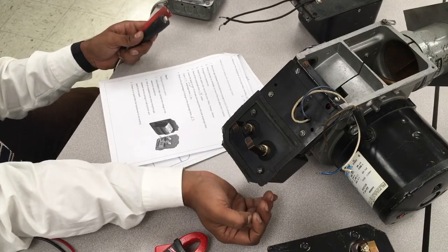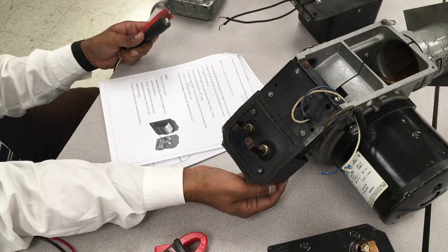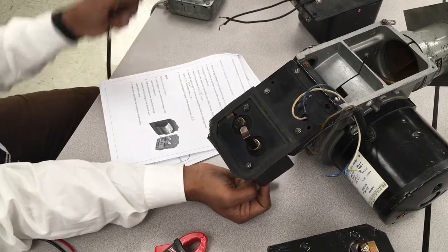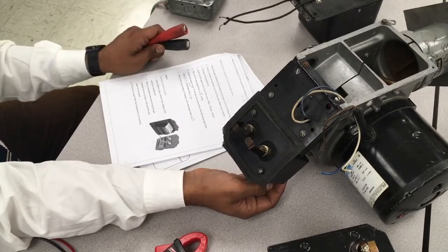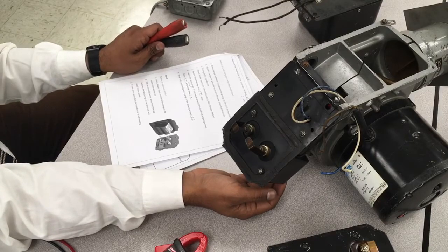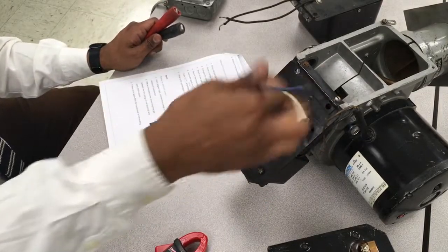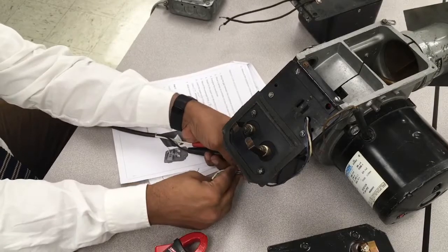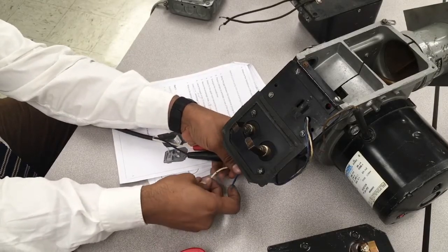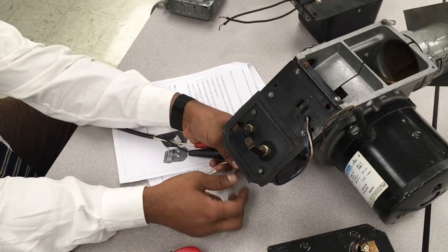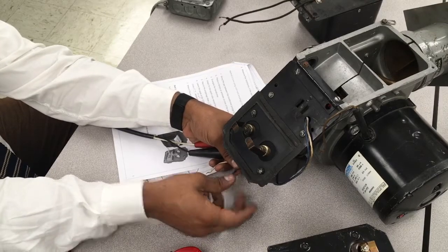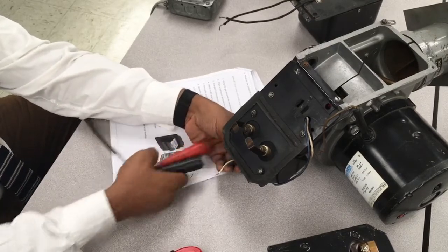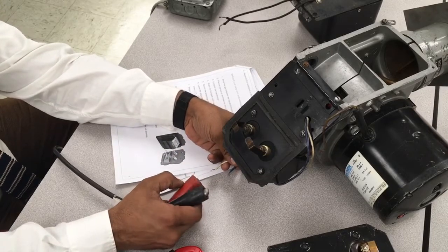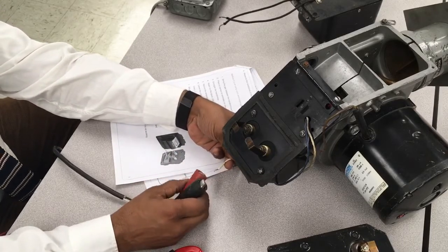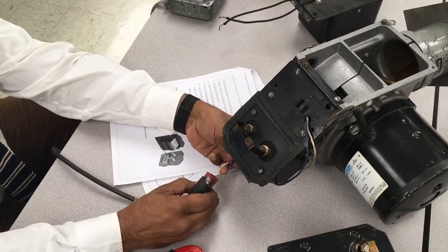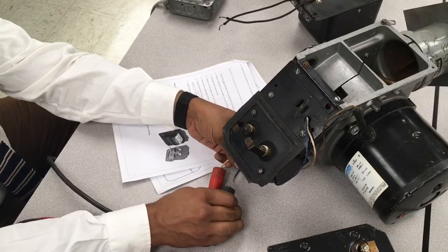It's supposed to give you up to 17,000 volts. You do not test those with a tester. They're either on or off, and it's really hard to put a clamp on it to see if it's on or off. So we pull out those prongs in here, and we try to jump the spark between the two prongs. Keep in mind, some manufacturers like Beckett say it's okay to do that, and some manufacturers say if you touch the prongs to each other, it will burn the processor.